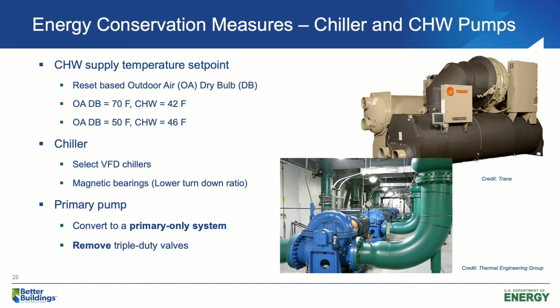If you need more chiller capacity and are in a position of purchasing new chillers, we would recommend you select VFD chillers and chillers with magnetic bearings. These two types of chillers can give you better efficiency at very low partial load ratio. For example, when those chillers are only 40% or 30% loaded, they can still give you very good efficiency.